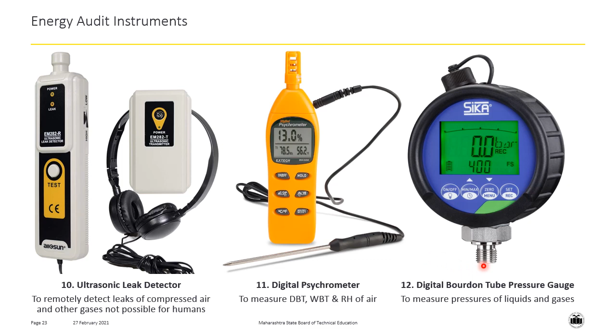The 10th energy audit instrument is the ultrasonic leak detector. It is used to detect the leaks of compressed air and other gases where it is not possible for the human beings to detect the same. The next instrument is the digital psychrometer used to measure the dry bulb temperature, wet bulb temperature, and relative humidity of atmospheric air in an industrial environment. The last instrument is the digital Bourdon tube pressure gauge, simply used to measure the pressures of liquids and gases.